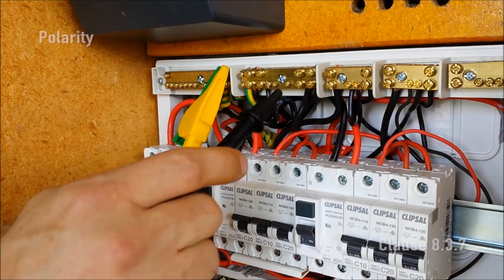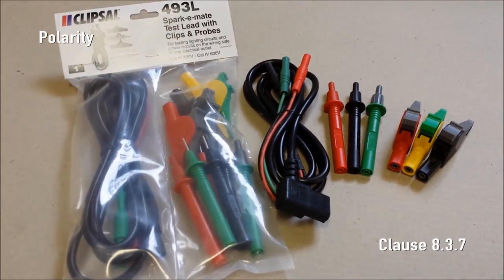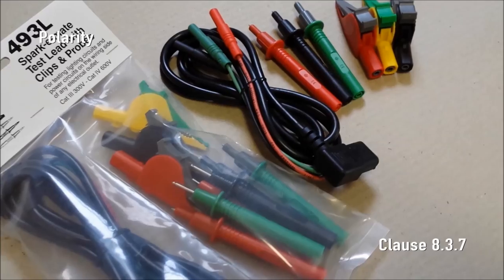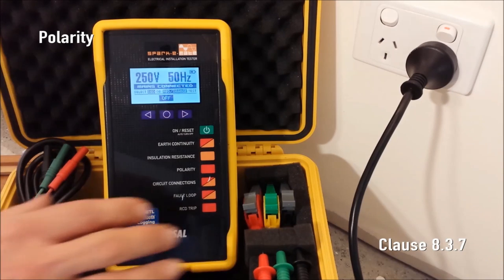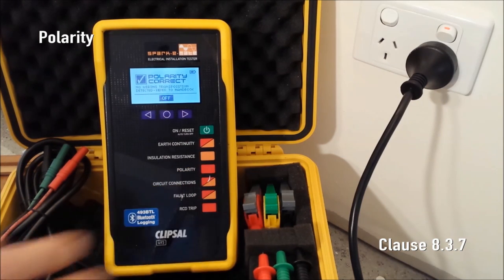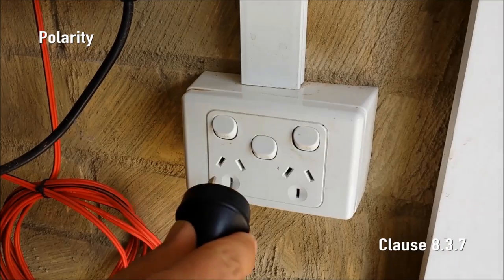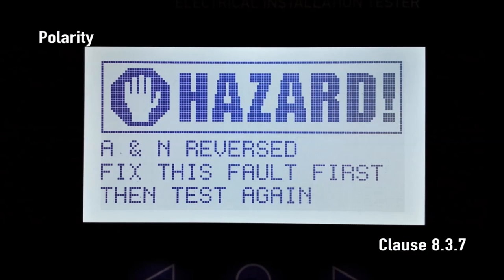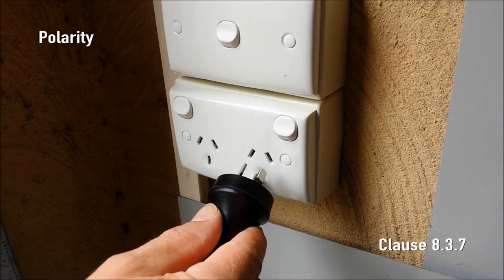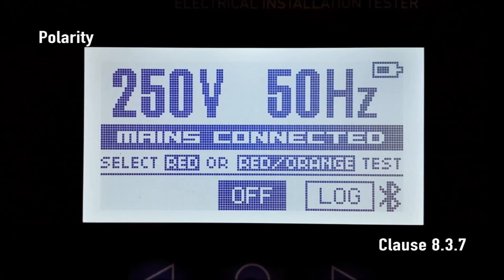Polarity. The polarity of the installation is first tested at the switchboard using the 493L test lead set. For your safety, testing the polarity of the consumer mains can only be performed using the CAT4 600V probes. For today's demonstration, we'll run a polarity test from a final sub-circuit at a socket outlet. We need to make sure that the active and neutral are not reversed. If the active and neutral are reversed, SparkyMate displays 'HAZARD: A & N reversed'. If the active and neutral are correct, SparkyMate displays the mains voltage and mains frequency.